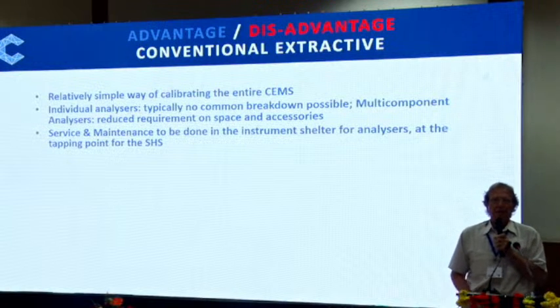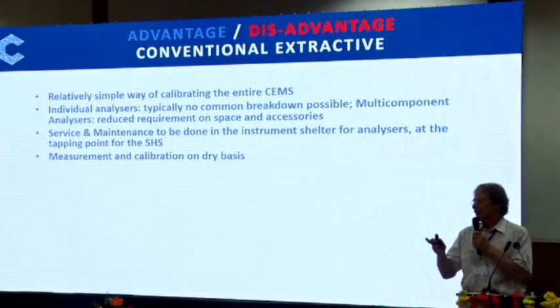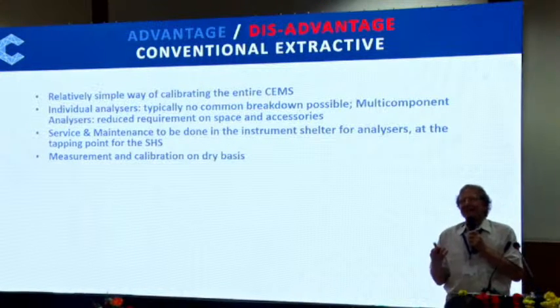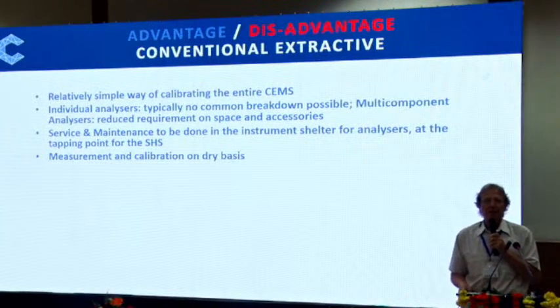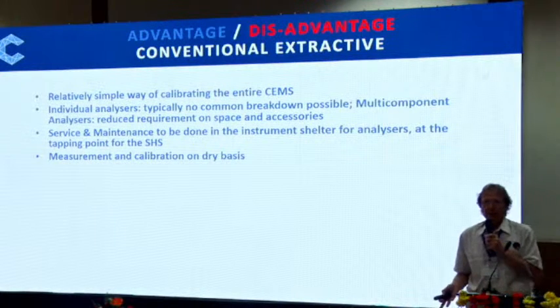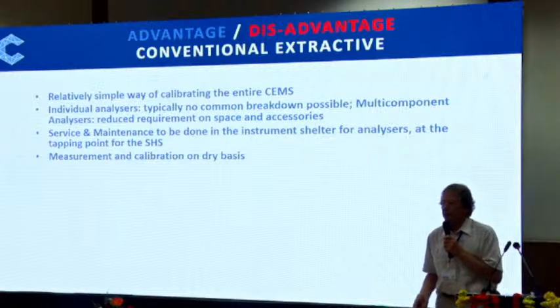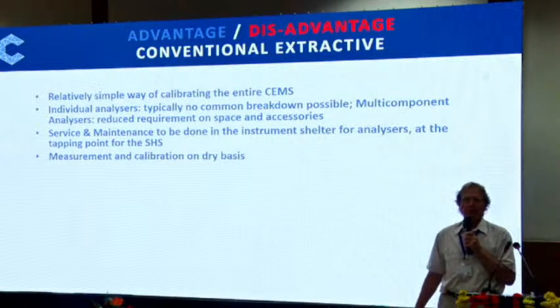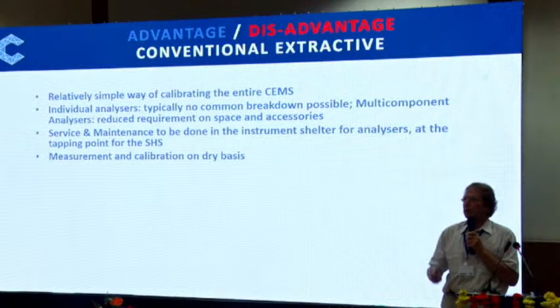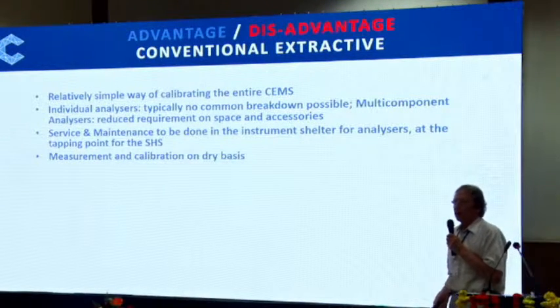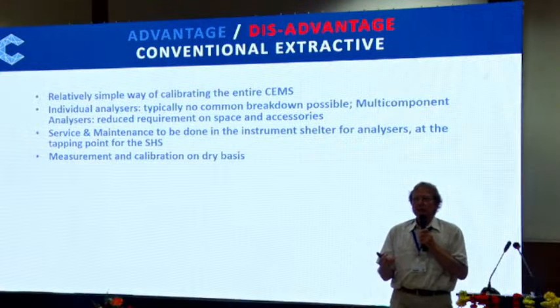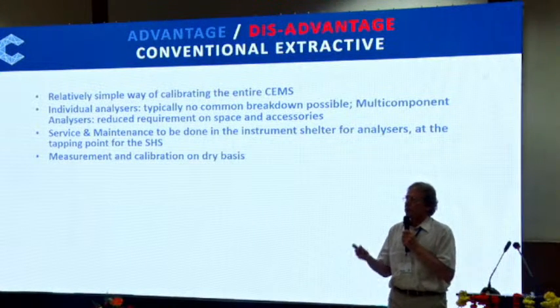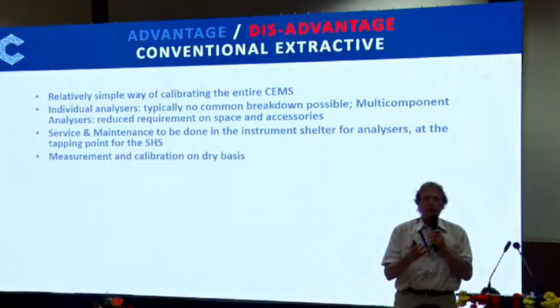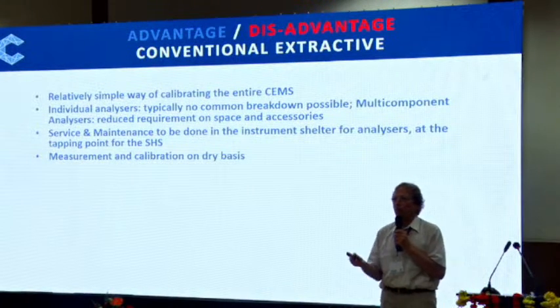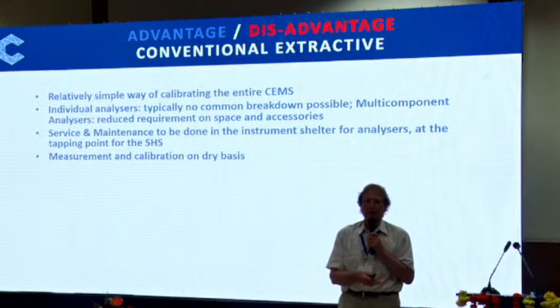So what's the advantage? Simple. We can easily span check and zero check, calibrating the entire CEMS. We have individual analyzers, as already mentioned. Service and maintenance for the analyzers is in the instrument shelter, not up on the stack, only for the sample handling system. And I'm taking out the condensate, so my measurement is on dry basis already. So I don't need to correct my gas analyzer data for the humidity, only my dust monitoring data.